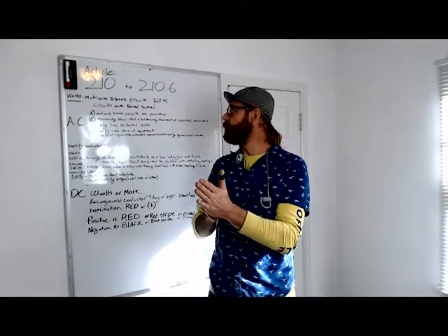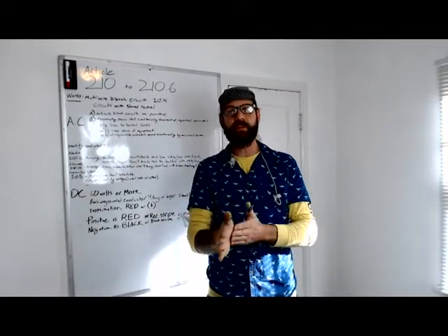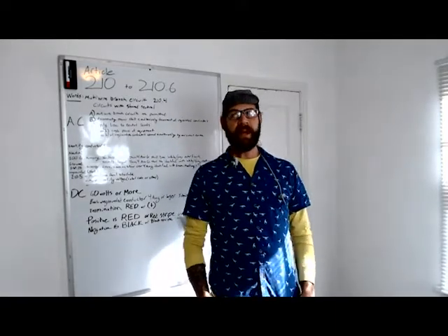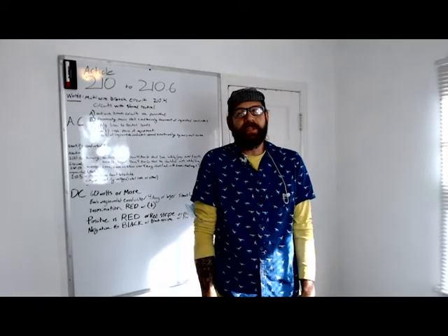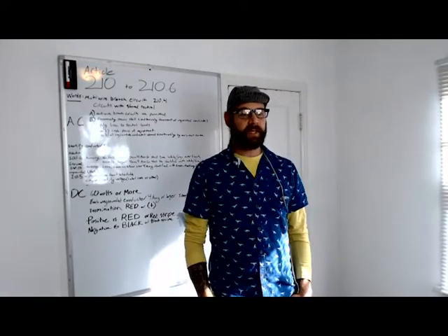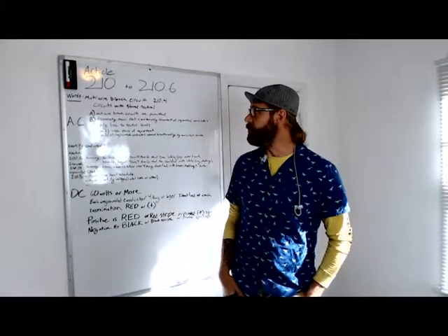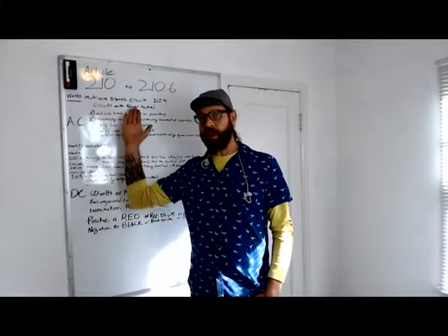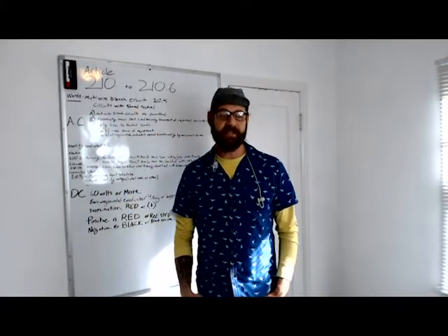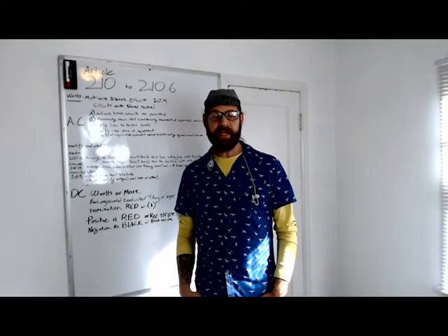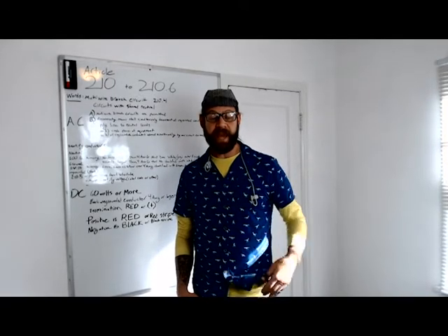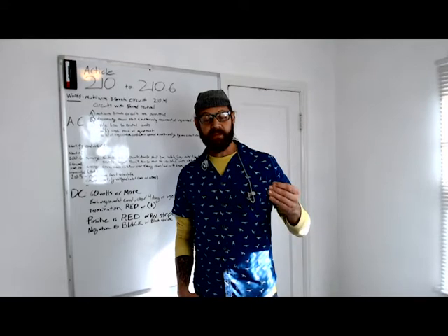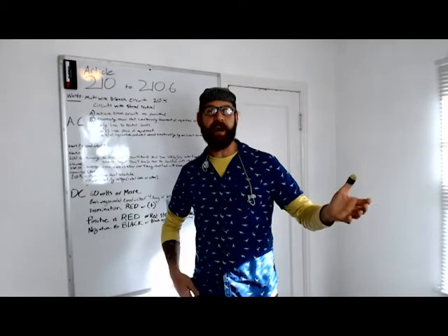Going to be doing Article 210 through 210.6, just the very beginning of the code. And what it's going to talk about is multi-wire branch circuits. This is kind of getting down to what this all means. So it starts out with the words multi-wire branch circuit. What essentially that means, if you don't know, is a circuit that has several ungrounded conductors, a couple of hot wires, and a neutral.